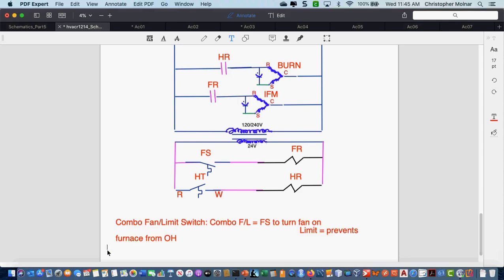Why do I want to prevent that furnace from overheating? It could cause a fire. Yeah. Now, in what condition? What would have to happen for that furnace to overheat? What would be the point of the failure? Bad airflow. So what would be my primary cause of failure or point of failure if my furnace is overheating? The blower or the fan? Yeah, the indoor fan or the blower might be bad or might not be starting.